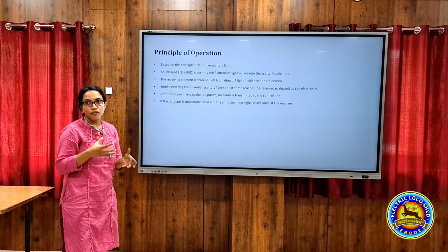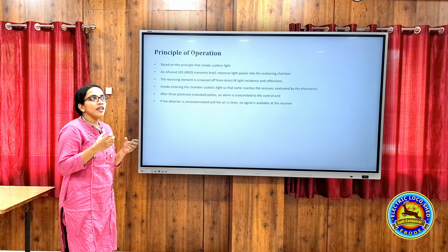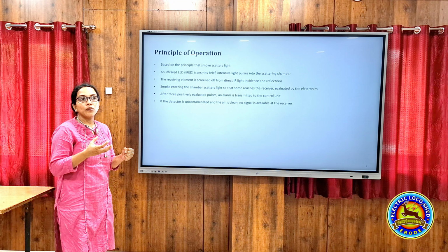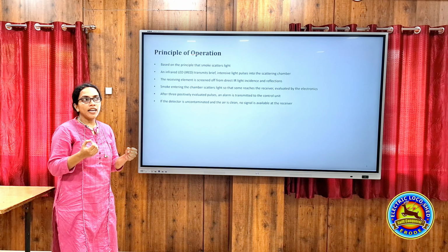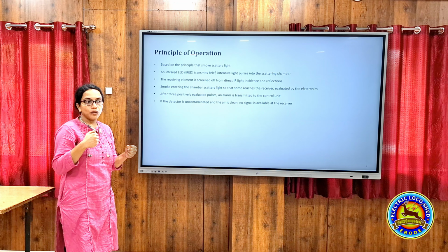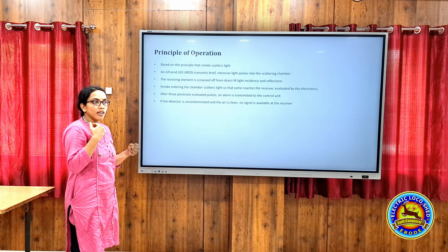The principle of operation of a detector is that light, when it travels through smoke, gets scattered. Usually, light from the source is not sent to the receiver. If there is smoke inside, the receiver will get the light. If there is no smoke, it won't get any signal at the receiver. And only after 3 pulses will the control unit get the signal.